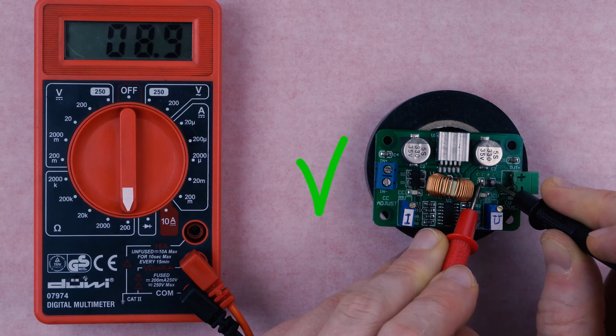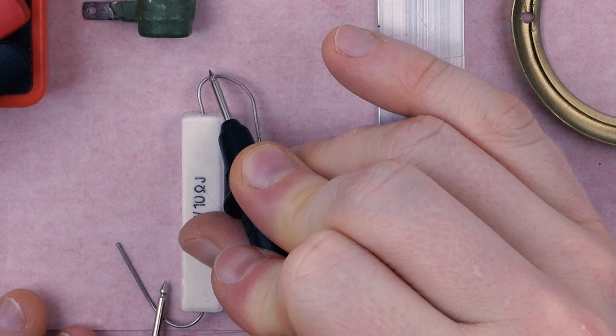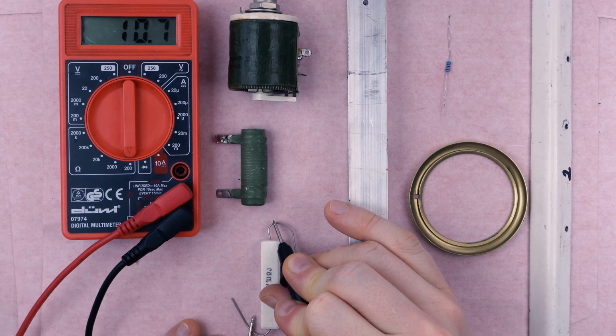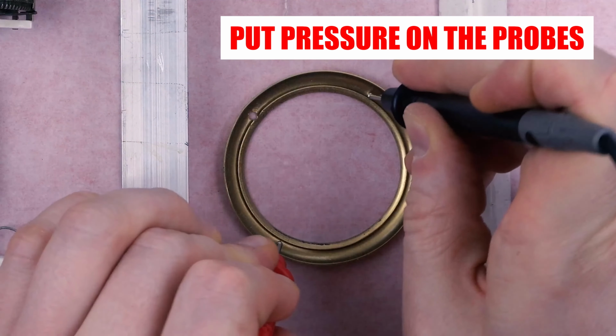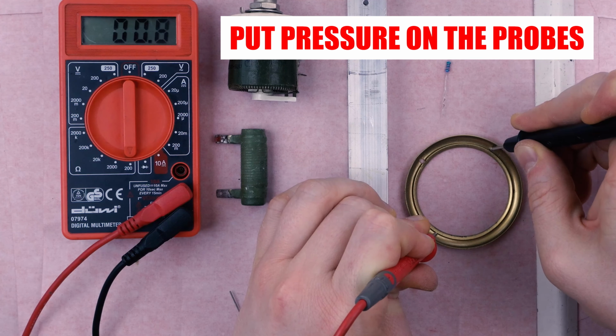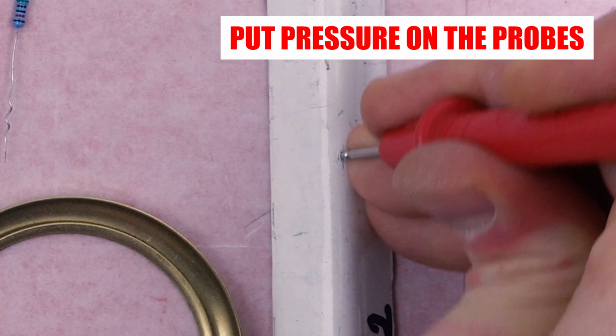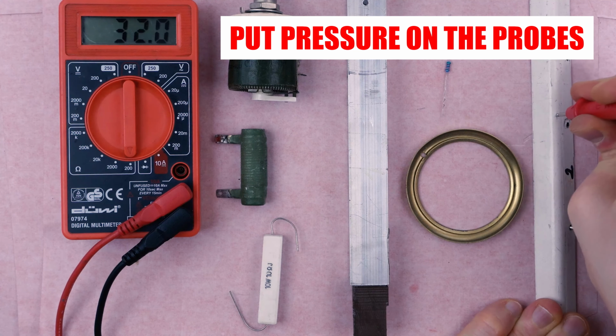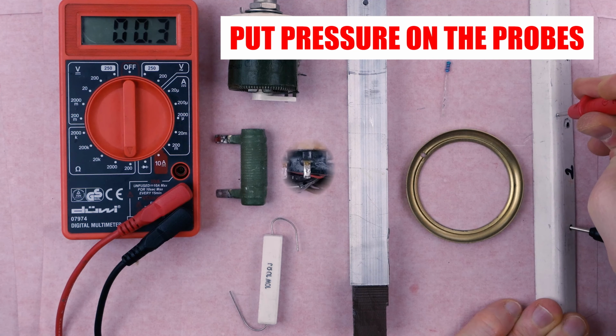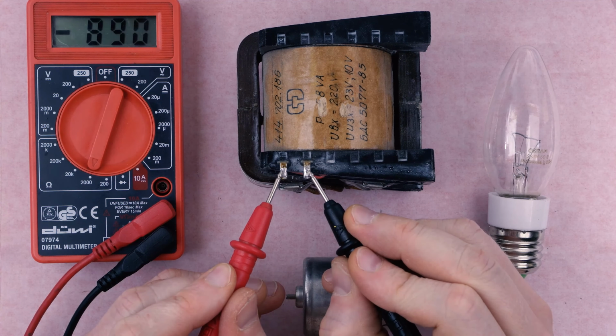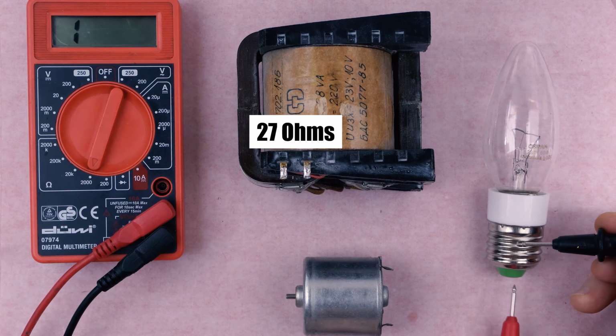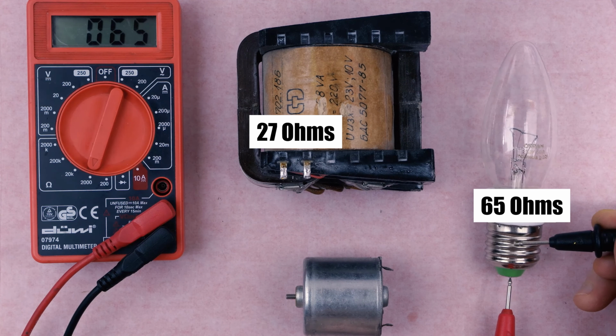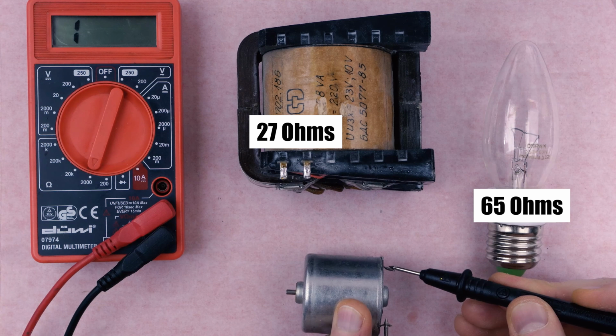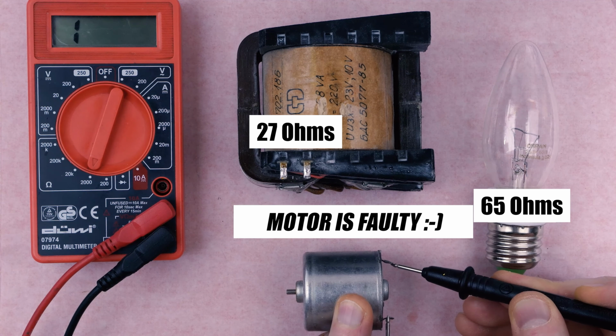Note that it is necessary to ensure proper electrical contact. Dust, dirt, moisture, and oxidation may affect measurement. In some cases, component leads may need to be cleaned. Resistance measurement mode is really versatile and can be used to test many other components. For example, you can check a solenoid or a transformer for continuity, or the windings of an electric motor for short circuits and ground faults.